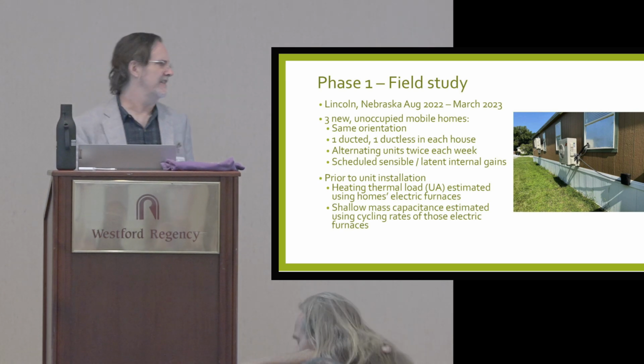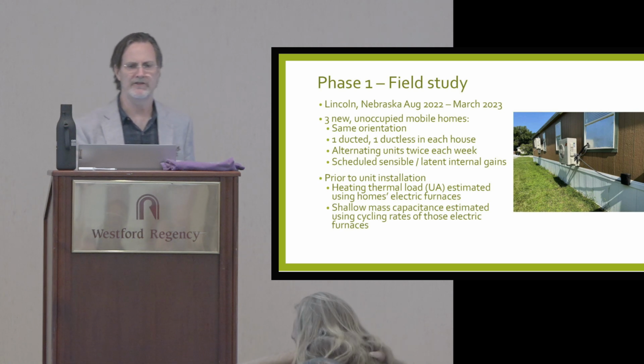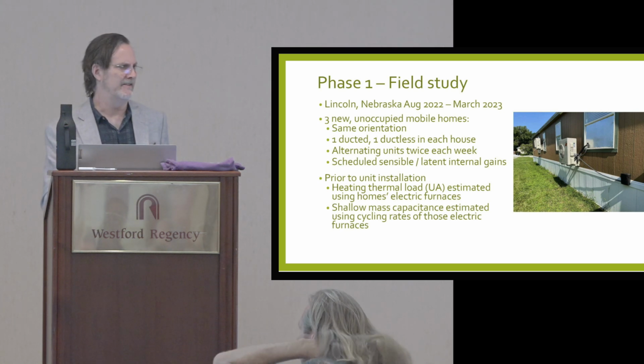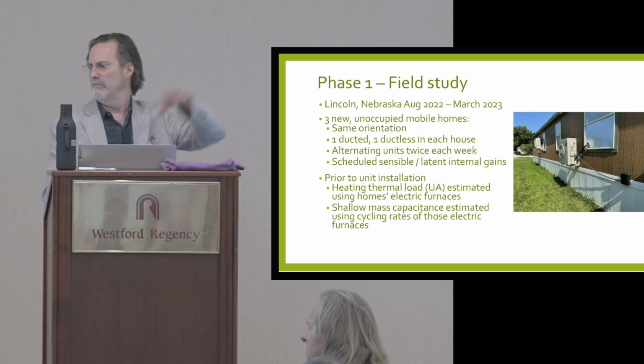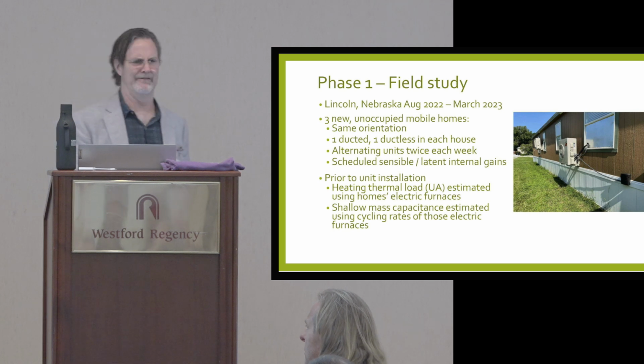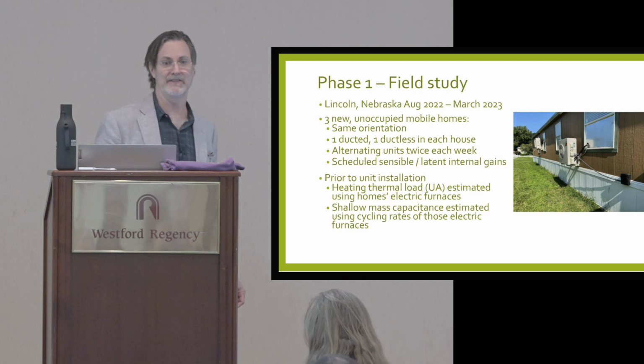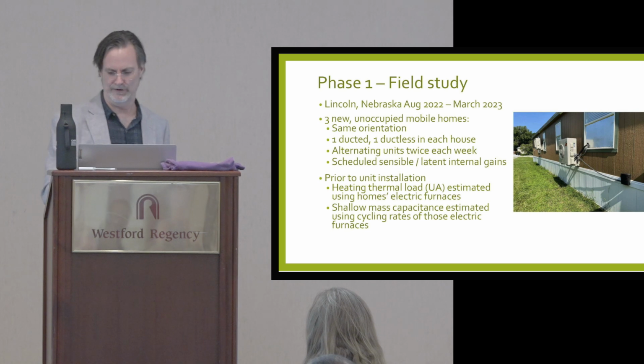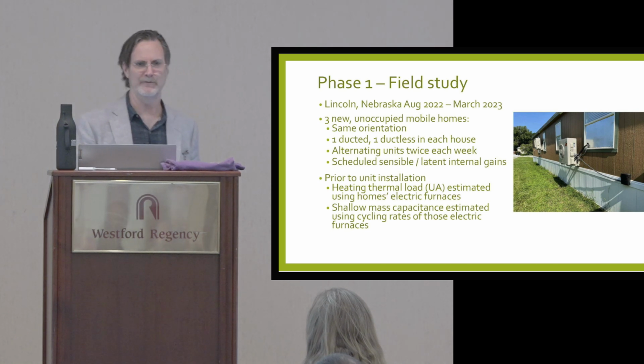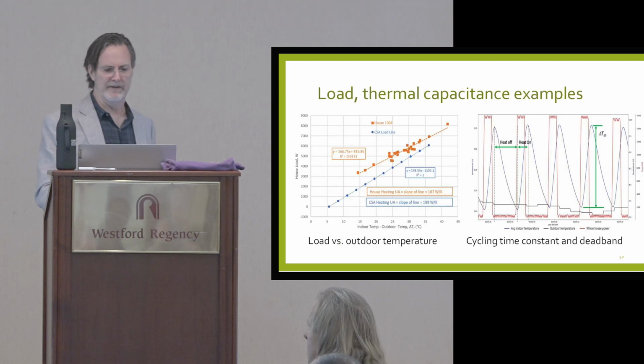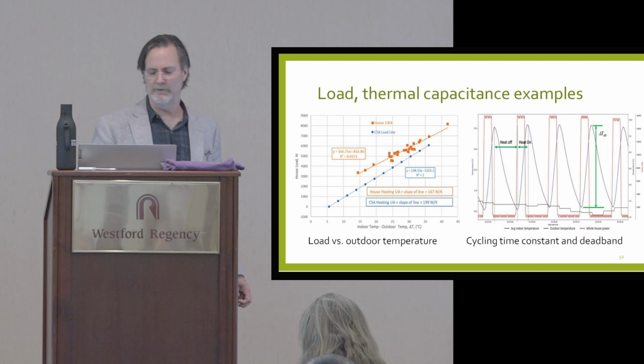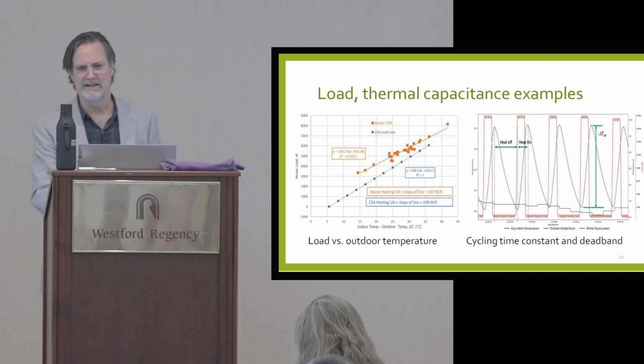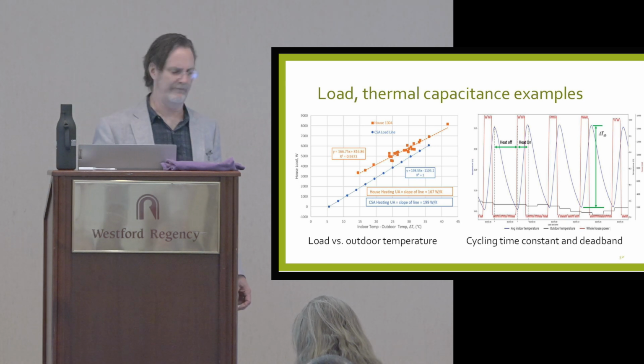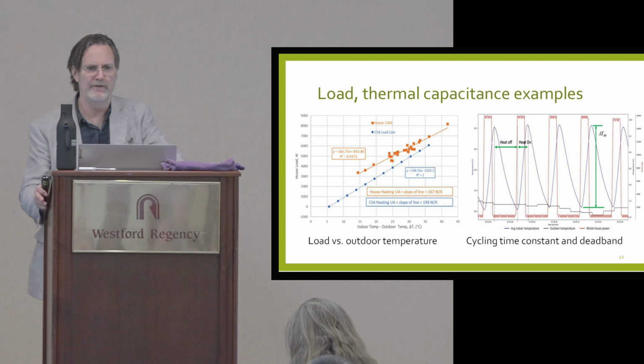We did a co-heat test a couple of nights to measure the UA of the buildings, and did cycling tests with the native built-in furnace. The 15 kilowatt electric furnace in these units shipped with them, so they were about three times the size they needed to be. But we got load curves and cycling rates and figured out that the loads were a little small.